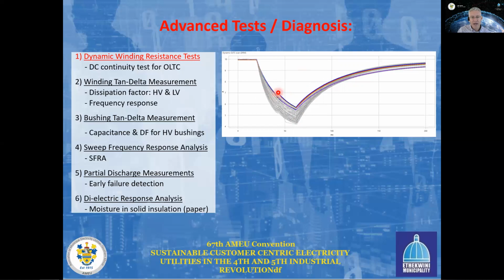You can see here, I've actually highlighted the results for the red, yellow, and blue phase of tapping up and then tapping down. You can see they're very close to each other, very much on top of each other. And these test results really indicate a very healthy and good tap changer.